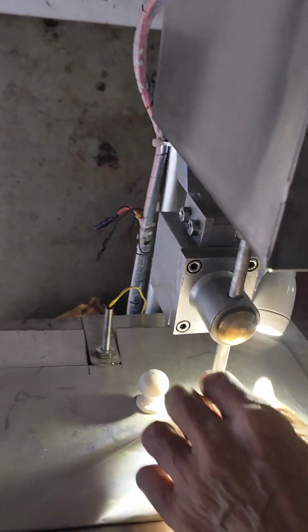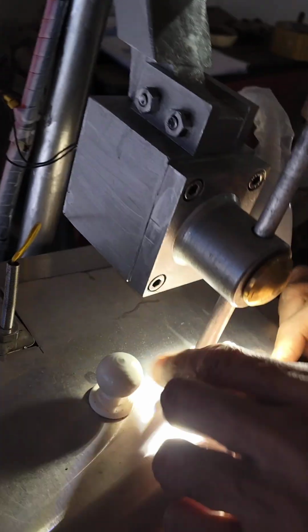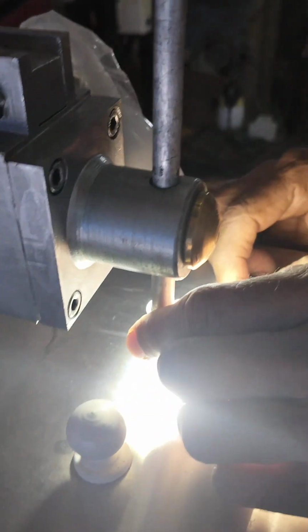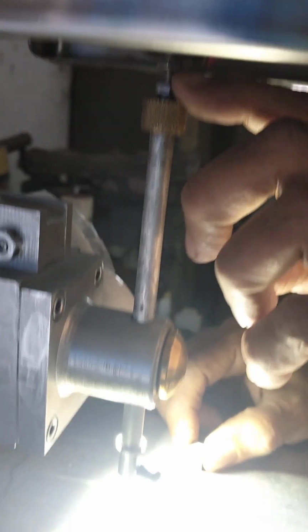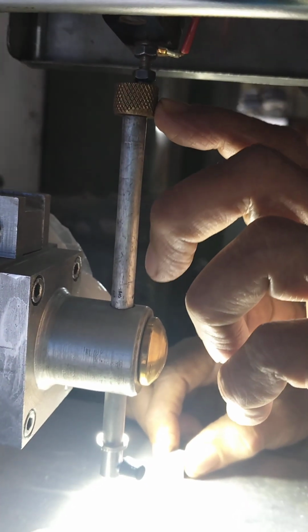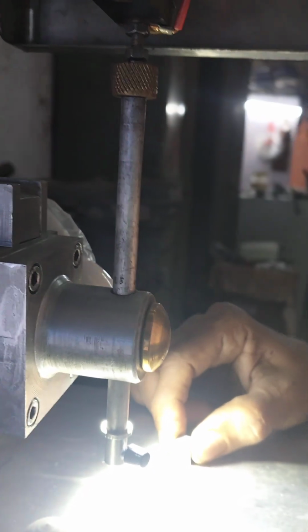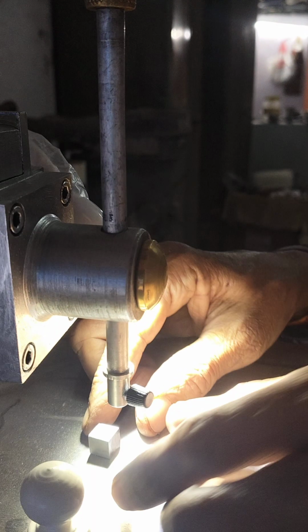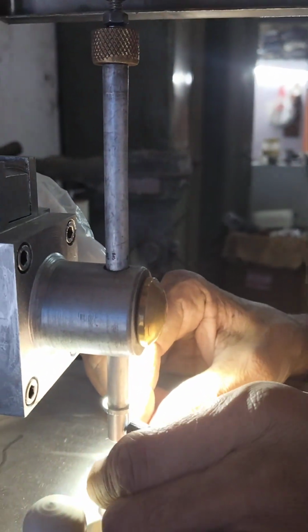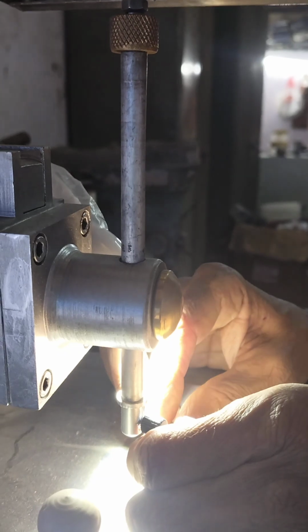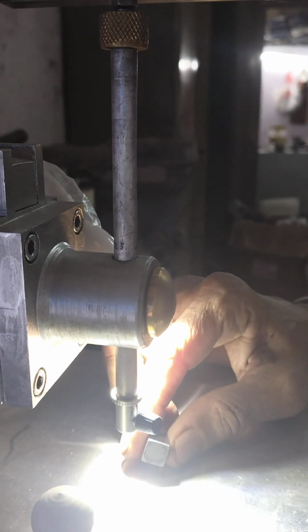Now I will show you how the calibration is to be done. First of all, you take the plunger and bring it to the top. There is a screw, the home screw. The plunger head is touching the screw, the home position. You have to keep this block which is having a 10 mm height. Whatever height is there should be shown in the penetration reading.